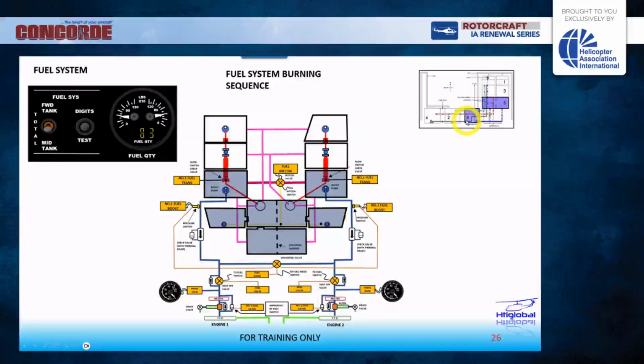But something interesting happens here. When this happens, both thermistors on the forward and mid cells are going to be dry. This situation follows a logic: within 30 seconds, the system shuts the transfer pump off automatically. The pilot doesn't have to turn off the switch. Everything is still on, the whole system handles this by itself.